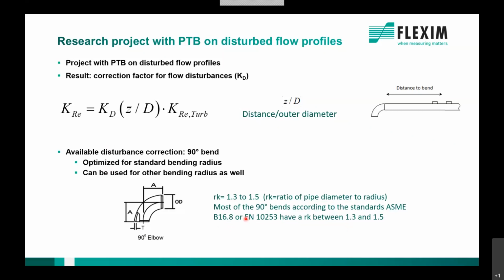If you have a different bending radius, you can still use it. The correction factor is the same. The only thing is that when having a different bending radius than this one, our uncertainty calculation has to take into account a higher uncertainty when not having exactly that bending radius. What that means for the uncertainty will come in the last slide I'm going to show today. For those who never heard that FLEXIM offers the possibility to make a customized uncertainty report, this disturbance correction is part of that, and I will show you how that may look.